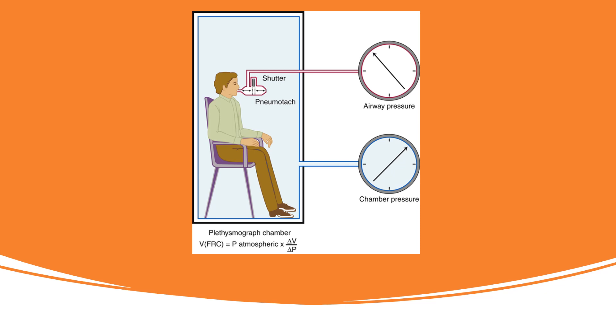Here are additional diagrams showing what happens on inspiration versus expiration within the body box. We look at box pressure and time — when the patient exhales, the flow signal becomes positive and box pressure becomes negative. When inhaling, the flow signal is negative and box pressure is positive. This changing relationship between box pressure and flow allows us to measure the patient's thoracic space changes and calculate functional residual capacity using atmospheric pressure times the change in volume over the change in pressure.